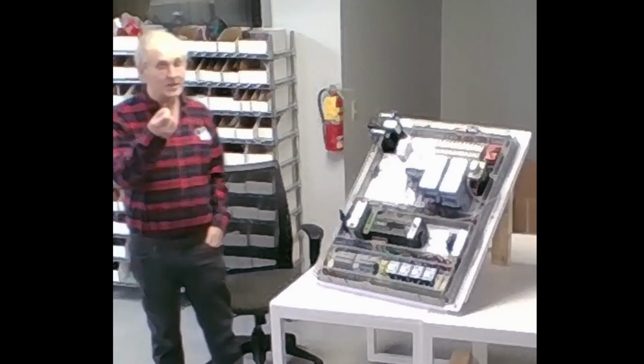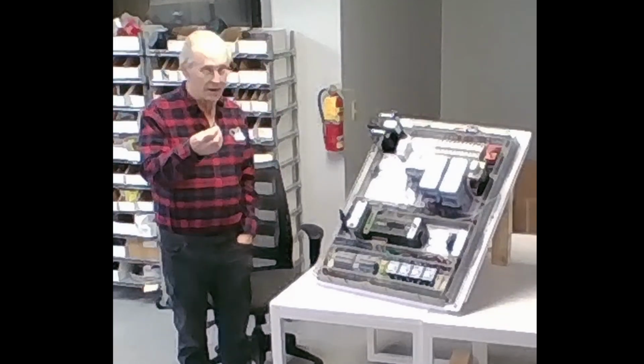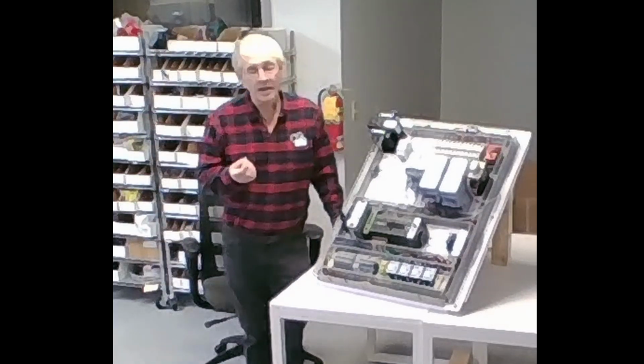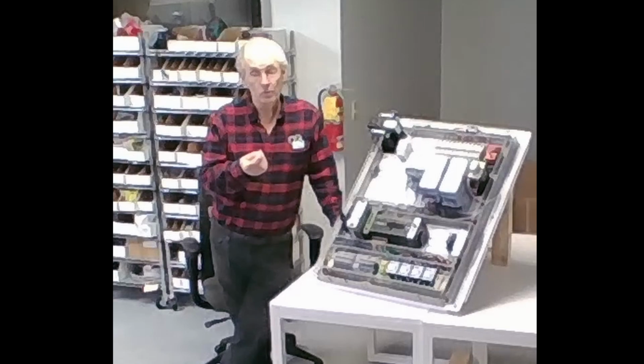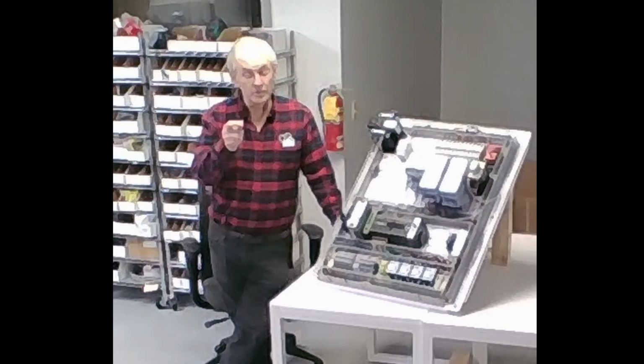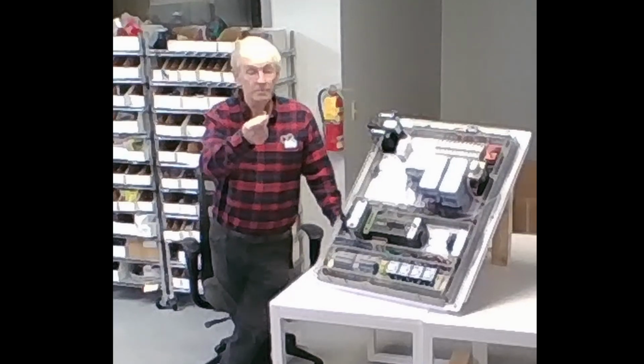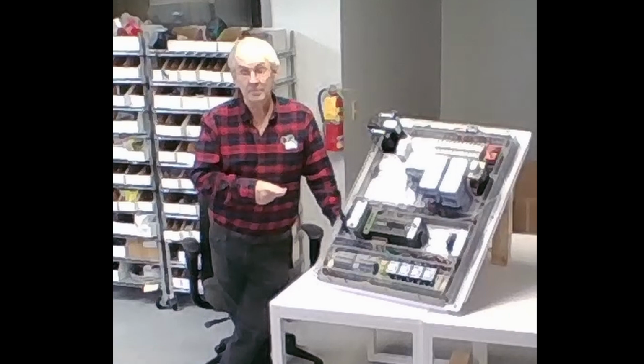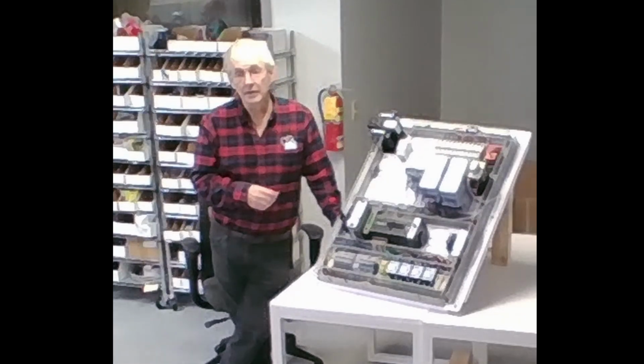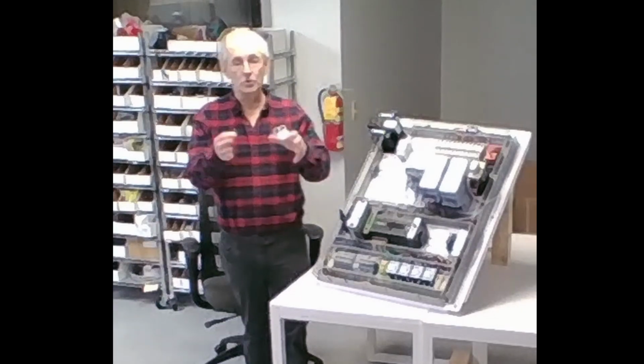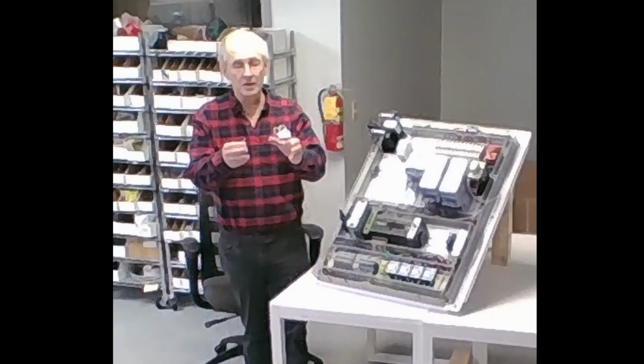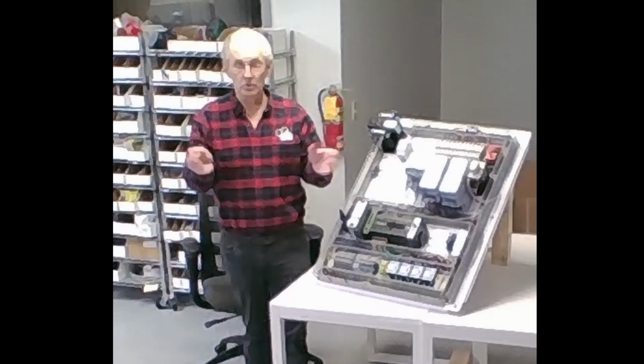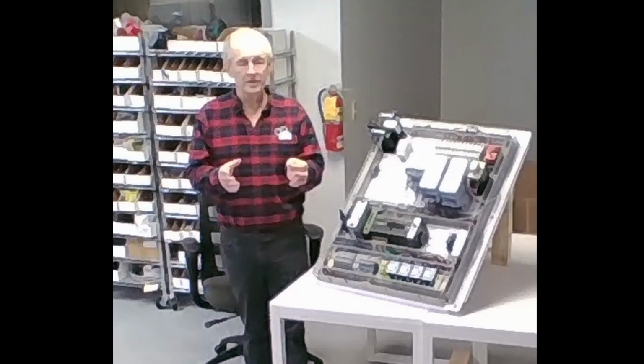Now, the fuses, these are glass. Then they have ceramic fuses. And the ceramic fuses, the difference is that the ceramic can take more heat and hold in more force. And in big fuses, big power fuses, the elements inside are typically pure silver, which is why the fuses are so damned expensive. The power fuses, because they're actually silver. And what they do is they use a whole bunch of little tiny links all sharing the load. And that's how they get the high current capacity, but also the ability to blow really fast. So, and then they're embedded in sand. There's a silica sand inside the fuse to absorb the arc.